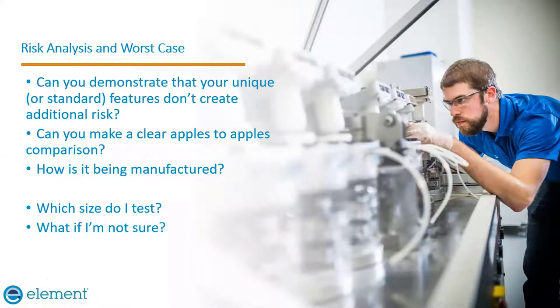Or this is one of my favorites. I have a customer arguing with me right now because the guidance document says FDA recommends you do biocompatibility per ISO 10993, and they're like, Michelle, it says recommends, it didn't say we had to. And I'm like, well, you better have a hell of a reason why you don't think you have to do at least cytotoxicity, sensitization, and irritation. So I just thought that was a really great point of yours.